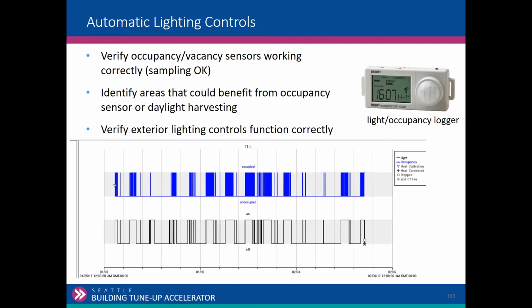If there's occupancy sensors or any kind of lighting controls, verify that they're working correctly. Do they turn the lights off? So that's one area. You could use a light occupancy logger. You could turn the lights off and wait, hit the timer, see if they come on automatically, or just observe when you walk into the bathroom, the lights go on. How long does it take for the lights to go off? And then on the exterior, you can verify that the lighting controls are working correctly. How would you verify that? They're off during the day and they're on at night. Pretty simple.